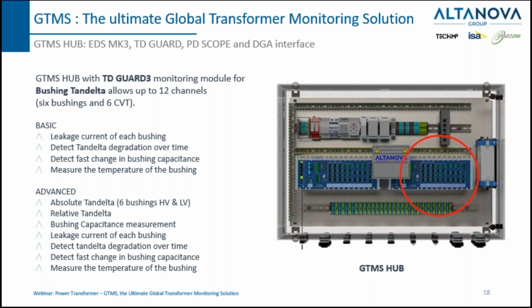This is another example, not only for the EDS, but for the hub, for the GTMS hub, with also the tan delta unit. This is here inside the red circle. This unit is capable of monitoring up to 12 channels. So basically 6 bushings and 6 CVT. We have in this case 2 configurations. One is the basic configuration, and we have also the advanced configuration. The big difference is that with the basic configuration, we can detect the relative tan delta values and some other parameters. With the advanced configuration, we can have the absolute tan delta value and some other important features.